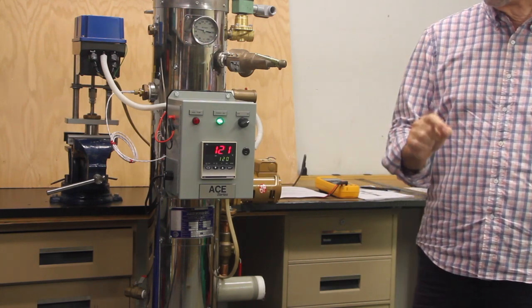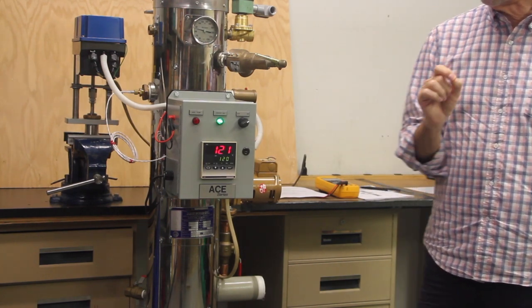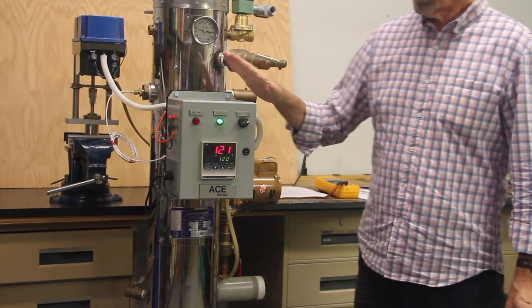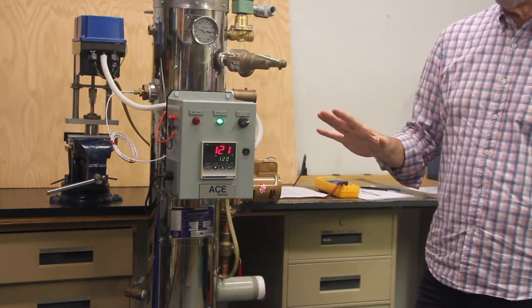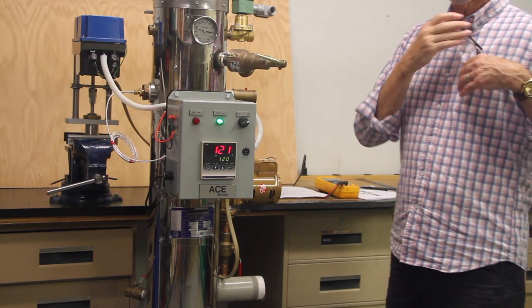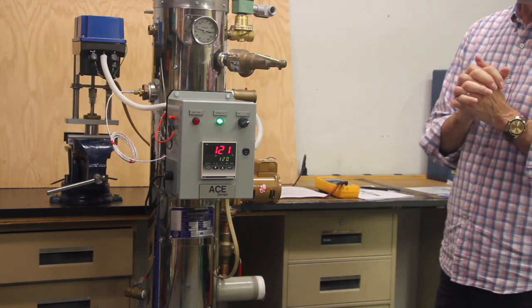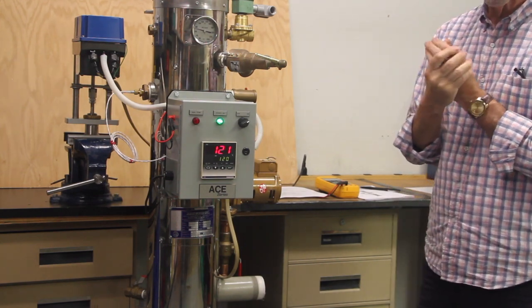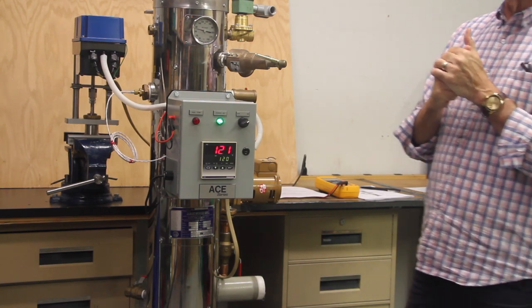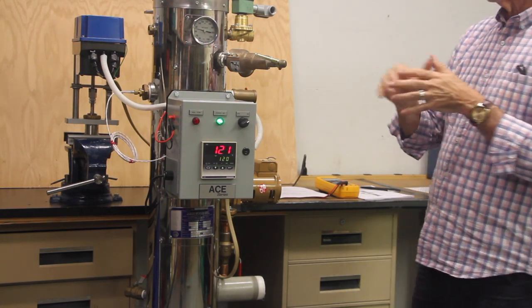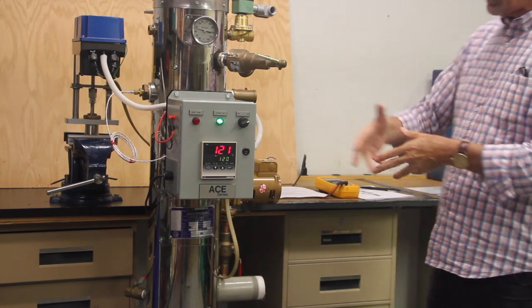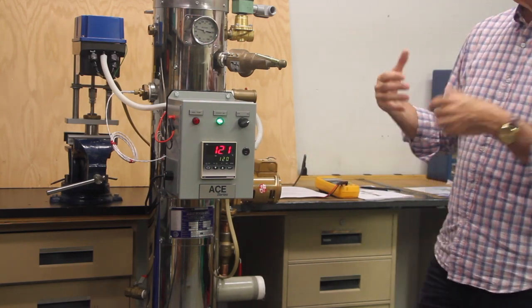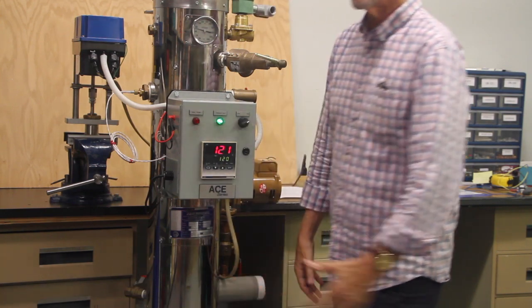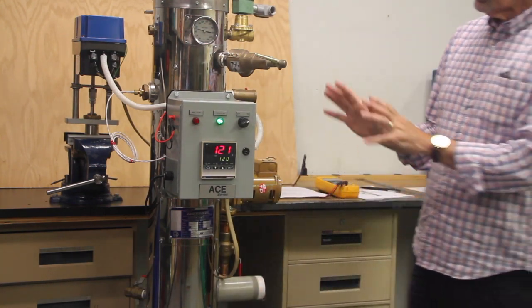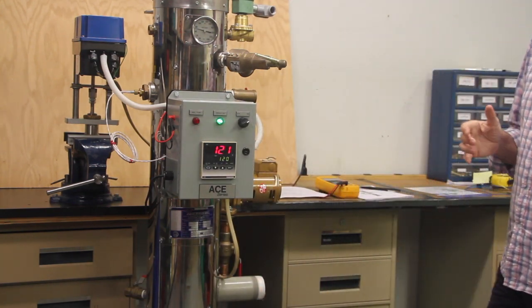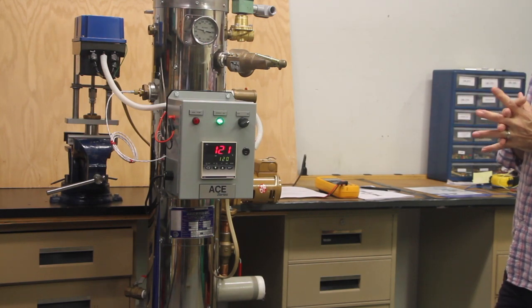If that pump is triggered on an aquastat or shuts off, we run the risk of this heater going into over temperature. Very important. A lot of years ago, people would run those building recirc pumps on an aquastat, or they try to save energy by turning it on low speed, and there's not enough flow going through the heater to radiate away that little bit of leakage on your valve. So that's a potential problem that I'm sure Tom can talk about even more.